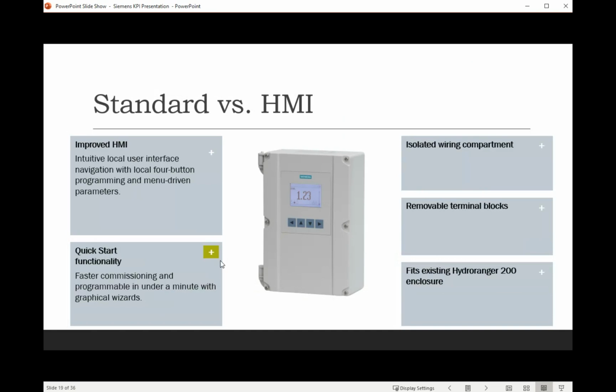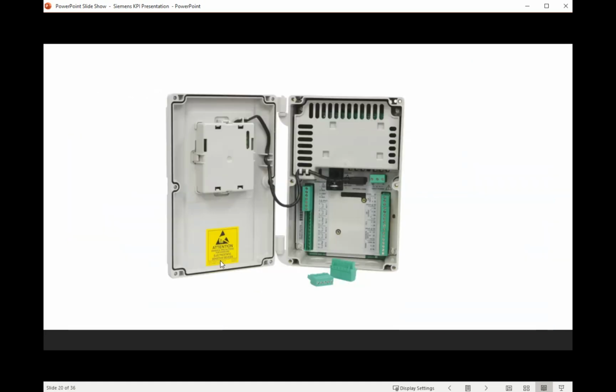So I mentioned that it's a much more intuitive local interface. It's 4 buttons. Everything's menu driven. The quick start makes it real simple to get a Hydroranger up and running in a matter of minutes. The wiring compartment is isolated. Siemens made the terminal blocks removable, so easy wiring. Everything's numbered. Pretty simple installation. And what I like the most is that it fits the existing Hydroranger 200 enclosure. So this is a picture of the inside of the Hydroranger. Removable terminal blocks. Everything's labeled.